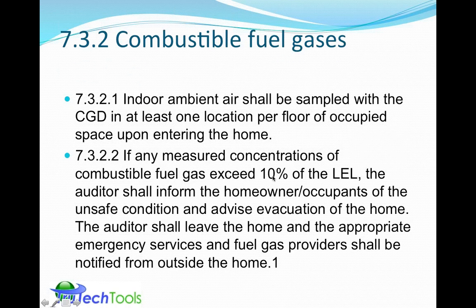For combustible fuel gases, there's a process here: sampling at least one location per floor before entering the home, the indoor ambient air. And then if any concentrations exceed that 10% LEL, so it either would be by the alarm or by the digital display, then you need to advise the homeowner.